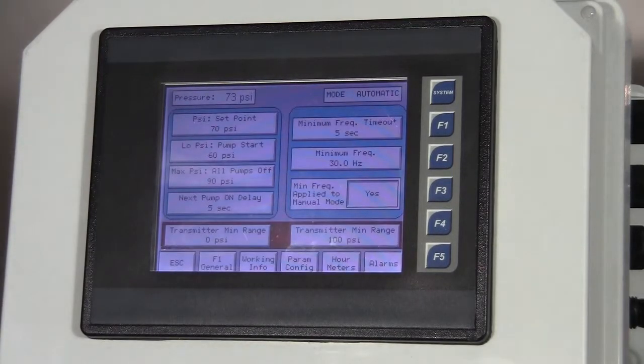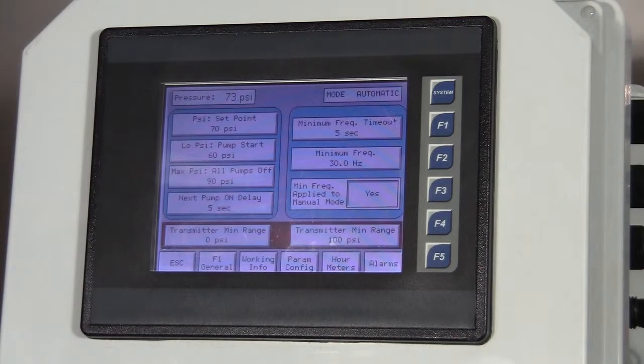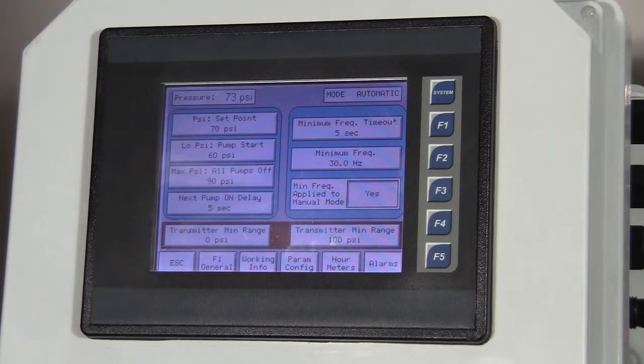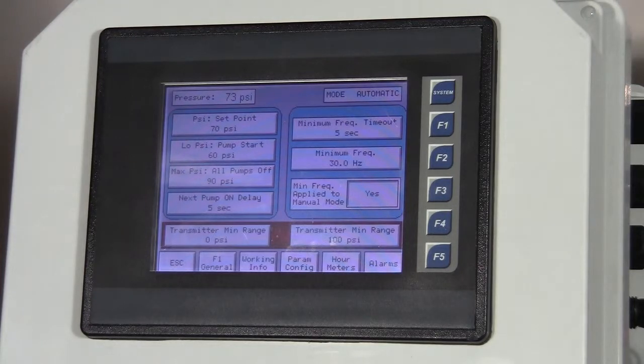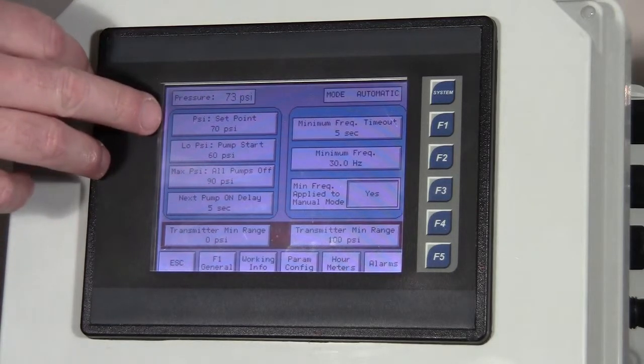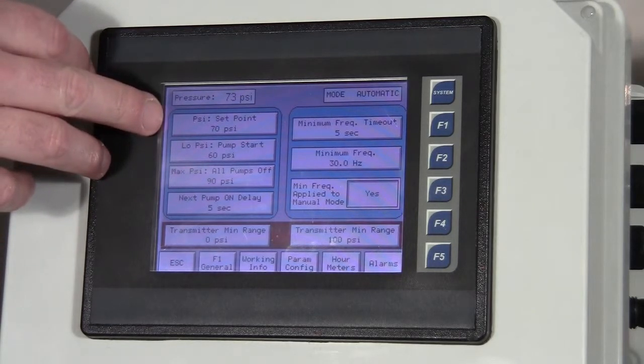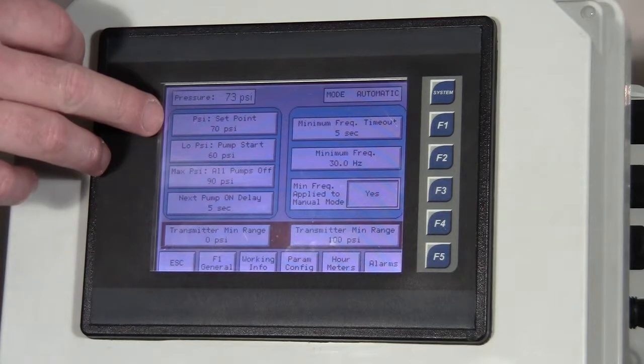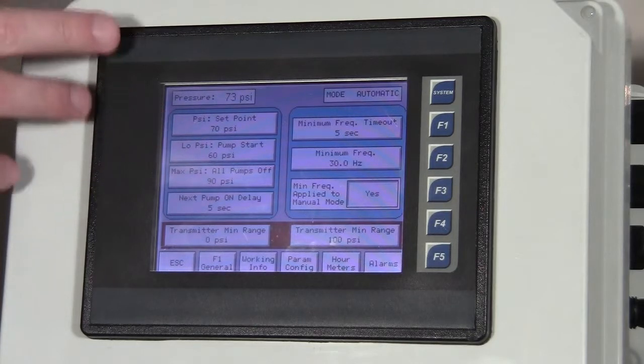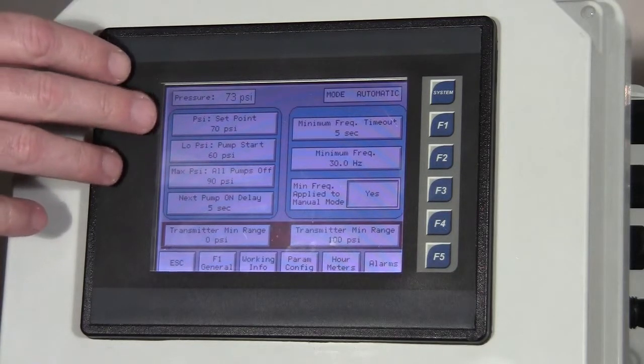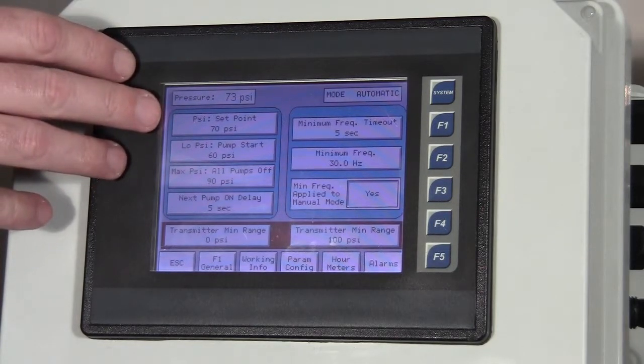The parameter config tells us our operating parameters as far as how it behaves at what pressure set points. So the first item is the actual set point. Right now it's set to 70 psi, so our pump system is going to try to maintain 70 psi.